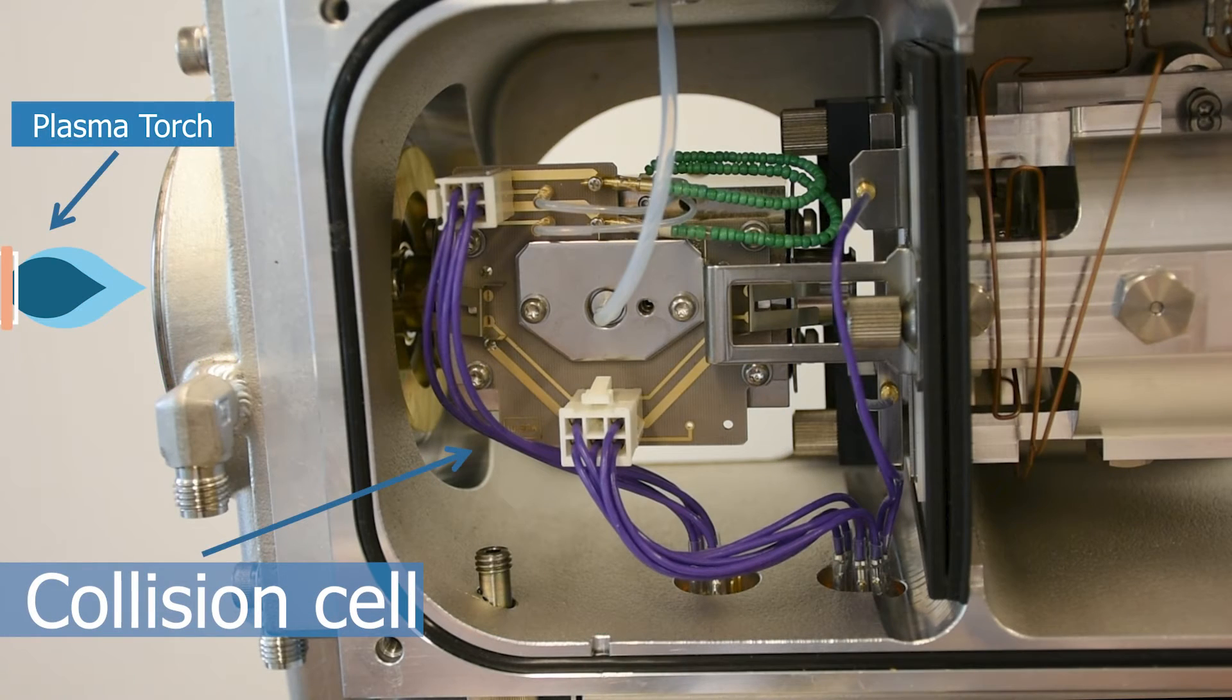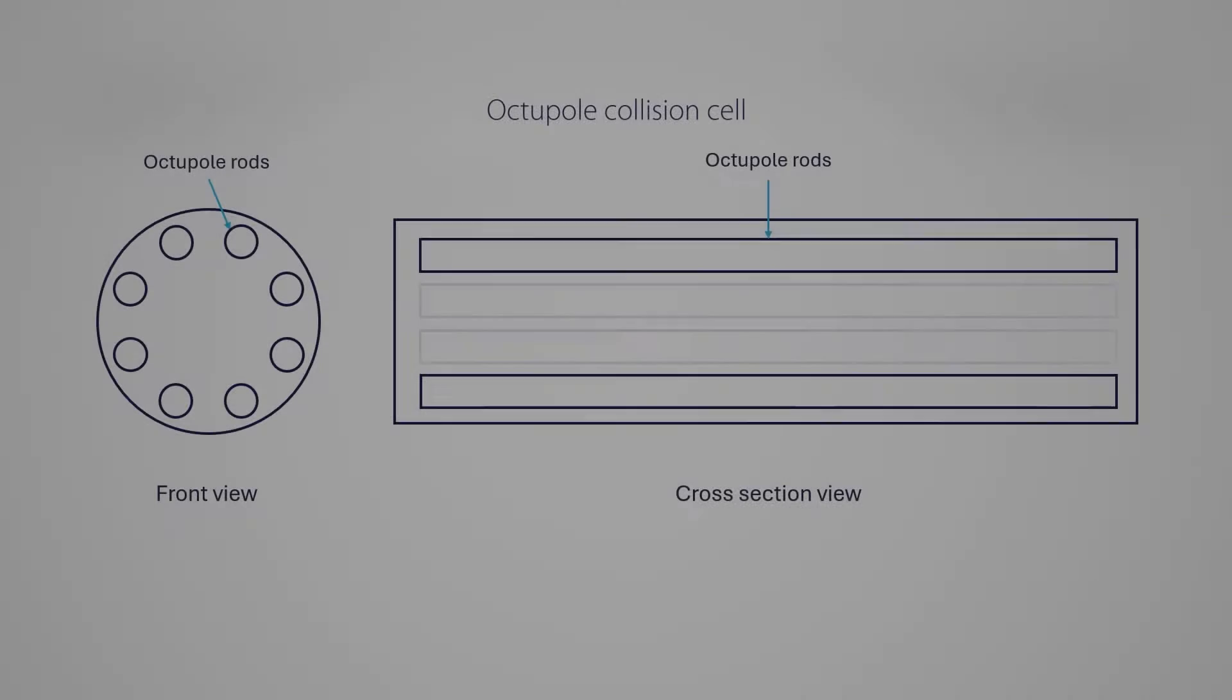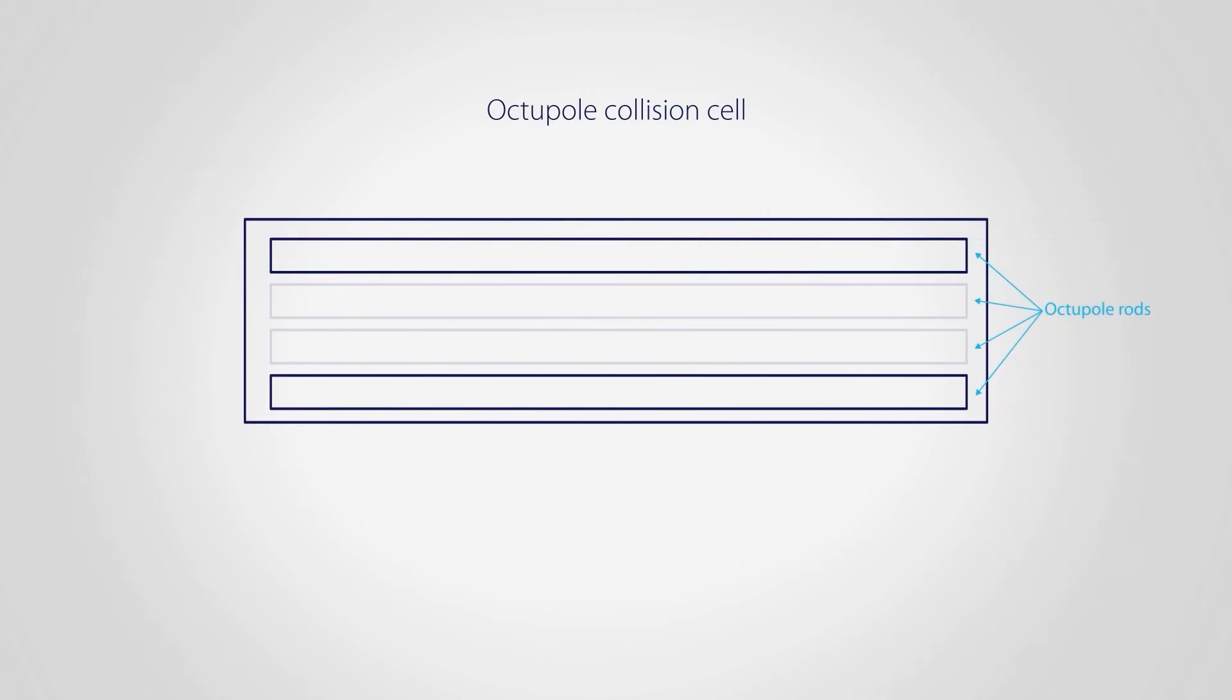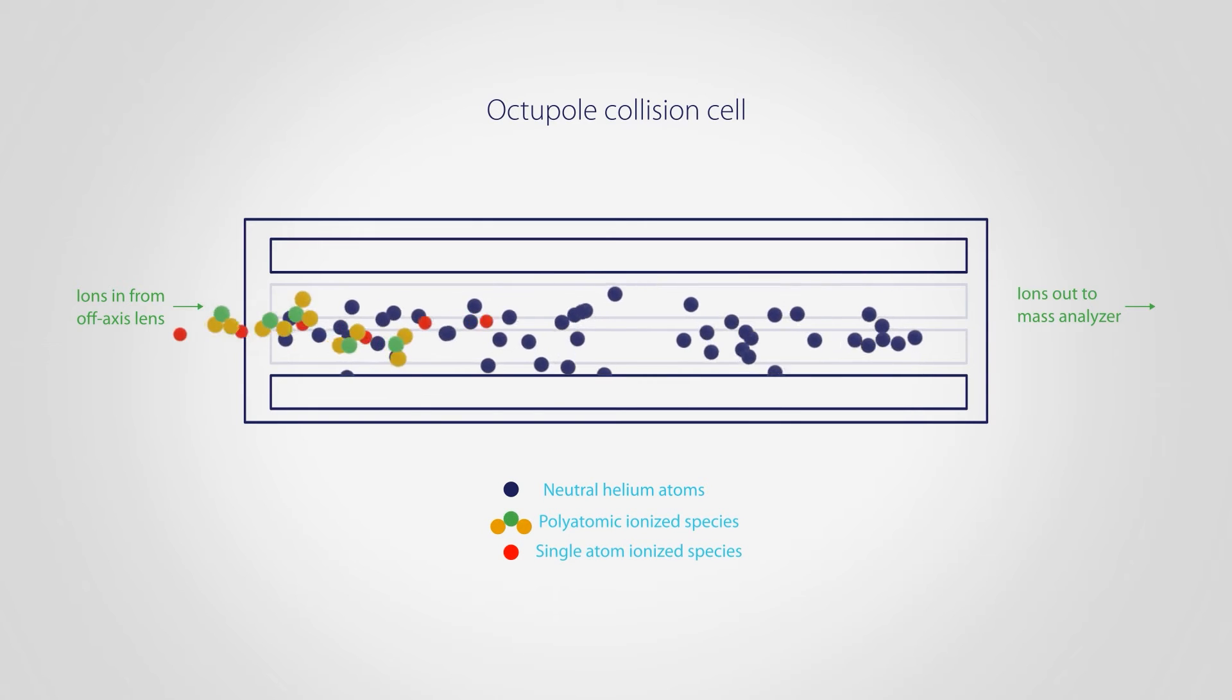The octopole collision cell is crucial for removing spectral interference by limiting polyatomic ions from entering the quadrupole mass analyzer. The octopole consists of eight charged rods inside a chamber filled with helium gas. Recall the ion beam contains both monoatomic and small polyatomic ions. As this mixture travels through the helium-filled collision cell, the bulkier polyatomic ions collide more frequently with helium atoms.